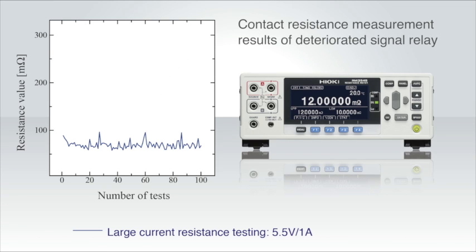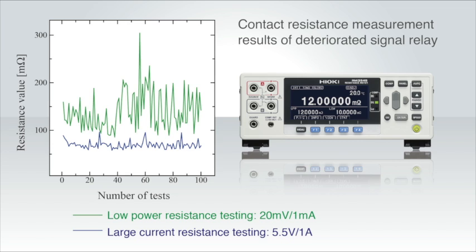Let's compare the measurement results from low power testing and large current testing. These are the results of using a large current to take the measurement. Now let's overlay these results with those taken from low power testing. As you can see, you can obtain higher resistance values using the low power resistance testing method.